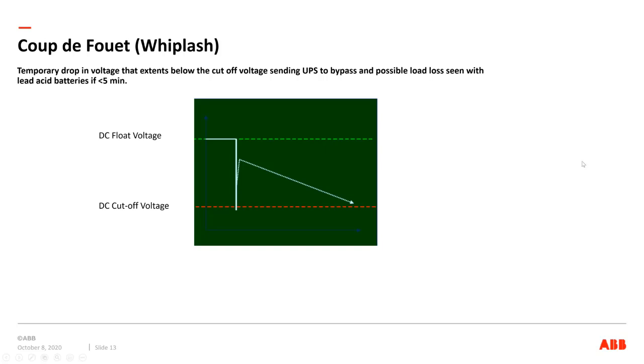So in the VRLA, like in the wet cell world, and actually for quite a while, 15 minutes of runtime was standard. But as the batteries really only needed to fill the gap between losing power and starting the generator, and vice versa, nobody really needs 15 minutes. So runtime requirements have gone down to the absolute minimum, and for a lead acid battery, that is 5 minutes. The 5 minute limit is that if you go lower than that, we get into the picture we have here, where the voltage actually drops when the load first hits the battery and can drop below the DC cutoff.